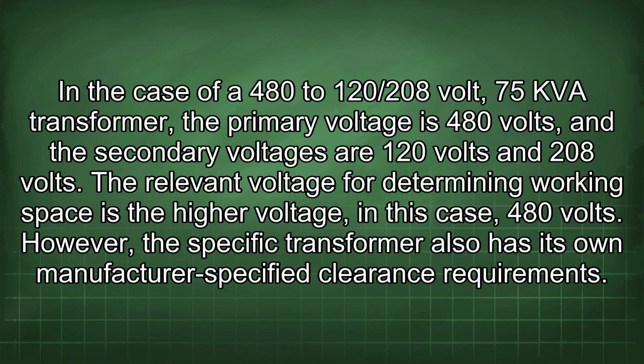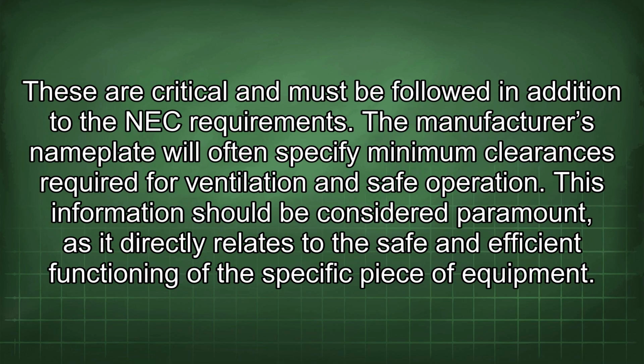In the case of a 480 to 120/208 volt 75 kVA transformer, the primary voltage is 480 volts, and the secondary voltages are 120 volts and 208 volts. The relevant voltage for determining working space is the higher voltage, in this case, 480 volts. However, the specific transformer also has its own manufacturer-specified clearance requirement. These are critical and must be followed in addition to the NEC requirements. The manufacturer's nameplate will often specify minimum clearances required for ventilation and safe operation. This information should be considered paramount, as it directly relates to the safe and efficient functioning of the specific piece of equipment.